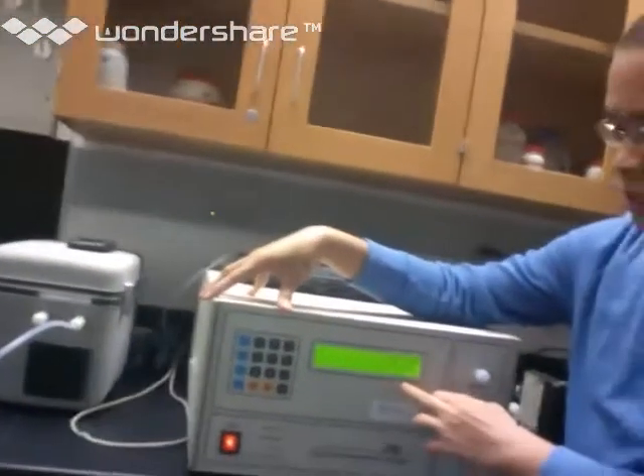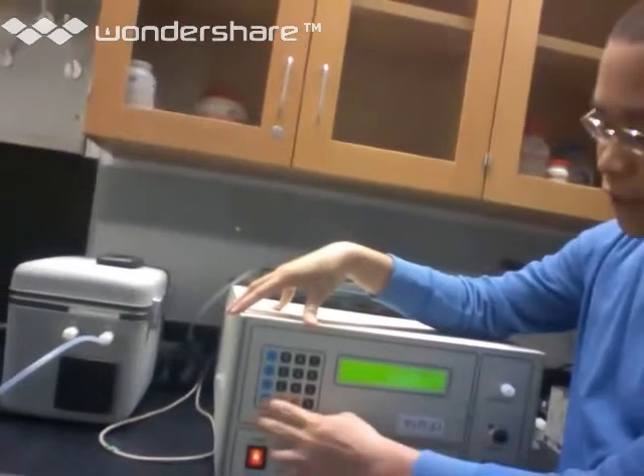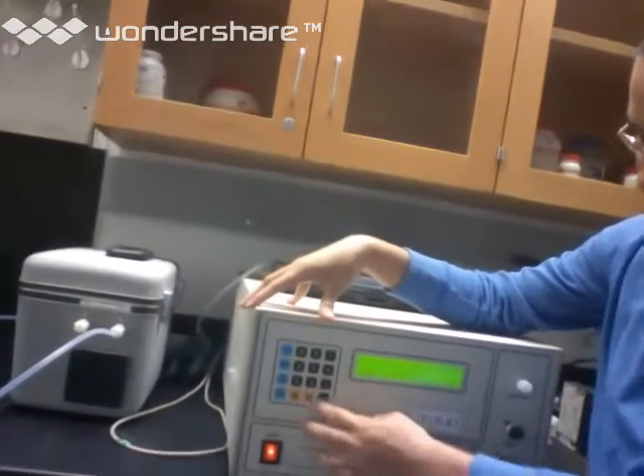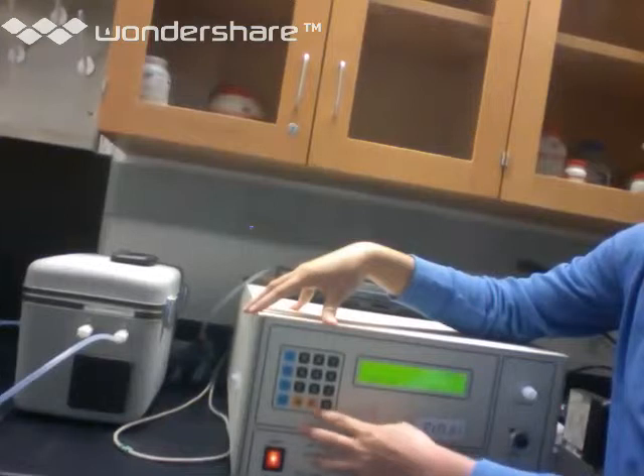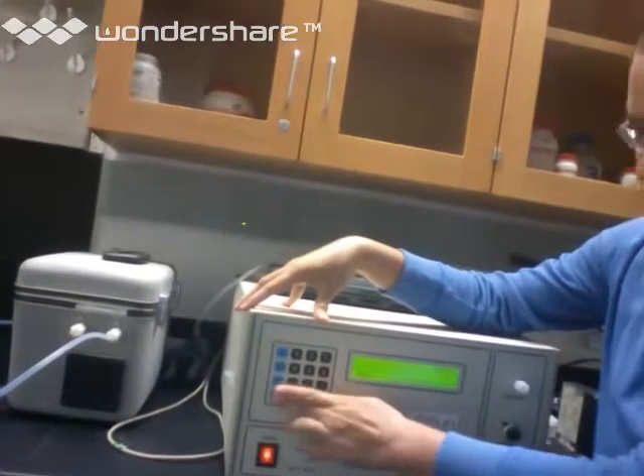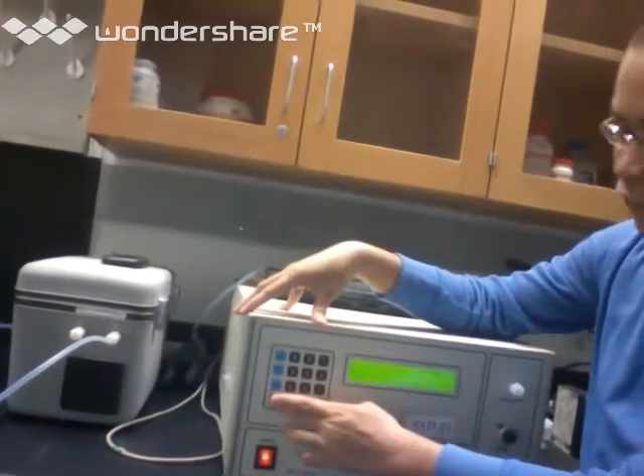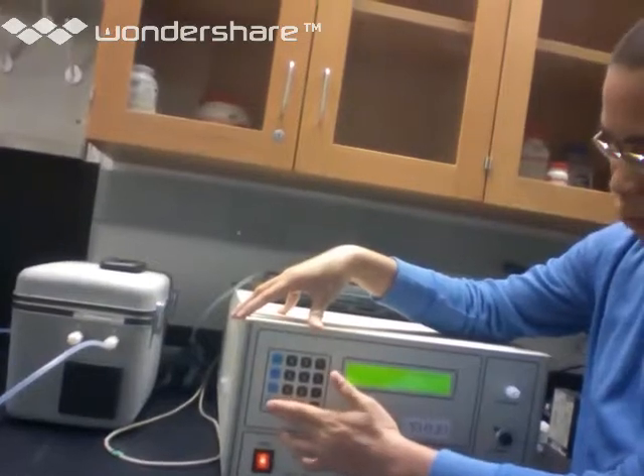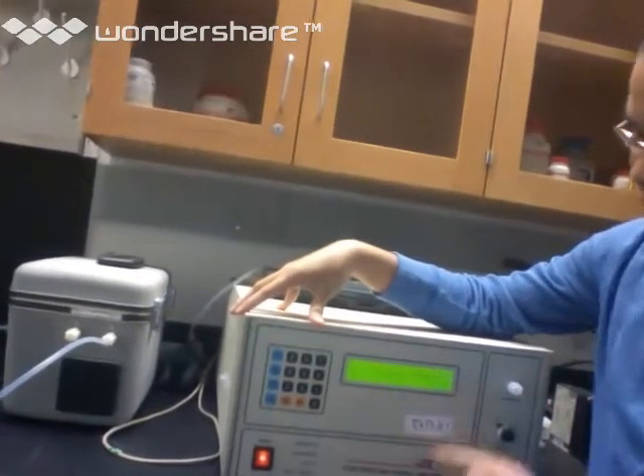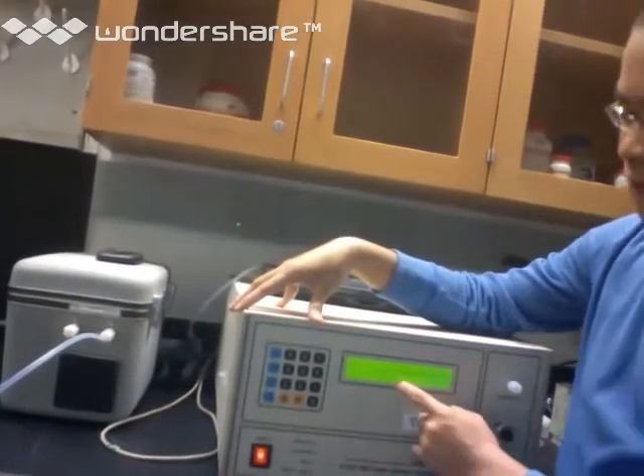Okay. So we're gonna switch the calibration type to inject, and then we're gonna press enter. We're gonna go back to calib. We're gonna hit enter here. And we're going to do a full calibration, always, and we're going to do both traps as well. It's going to ask you to enter the amount to inject in nanograms. So if you follow me, I'll show you where you get that number.